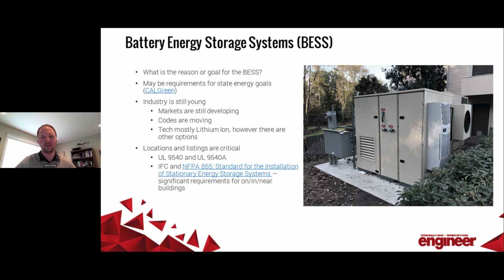UL 9540 and 9540A are the two main listings you want. 9540 covers battery system operation and fire requirements, and 9540A is a flame spread test you'll really want if you're going to be in, around, on, or near a building.